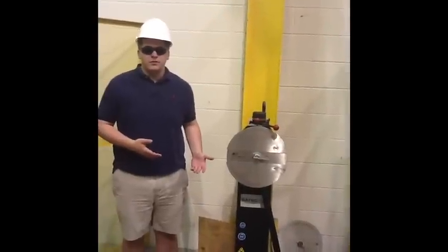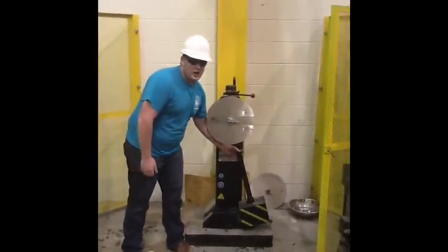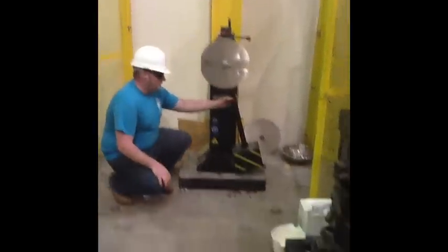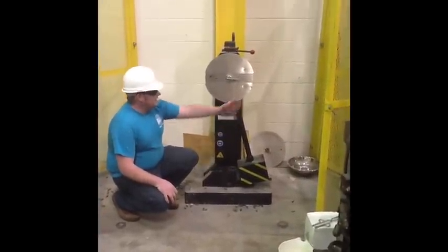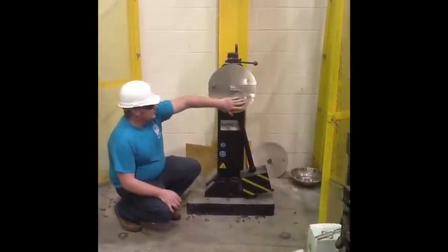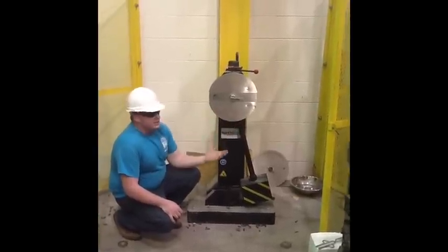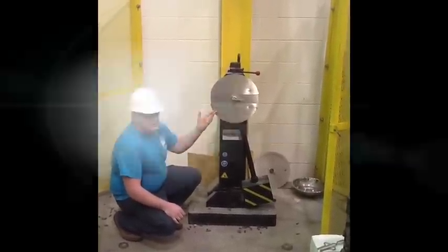Today we are going to run the Charpy V-notch test on steel. This is a Charpy V-notch machine. It consists of a large hammer that falls and strikes a piece of steel placed between these two marks. When it falls, it brings the pendulum around and strikes the steel, and the amount of energy absorbed by the steel is what's recorded on the dial.